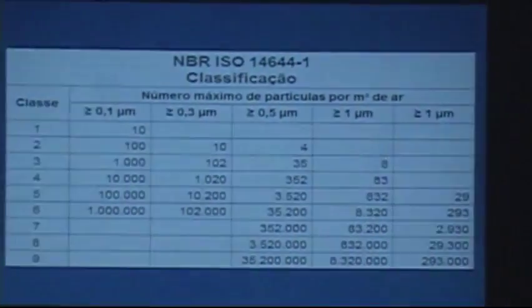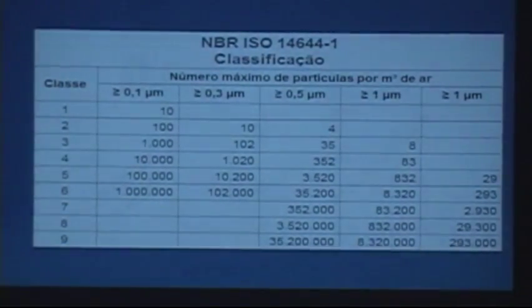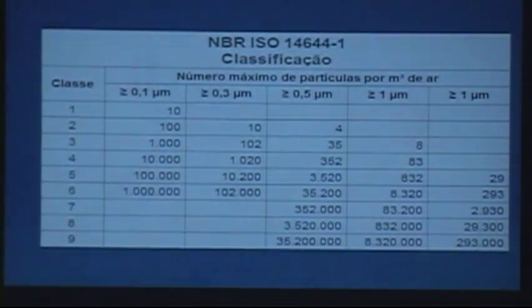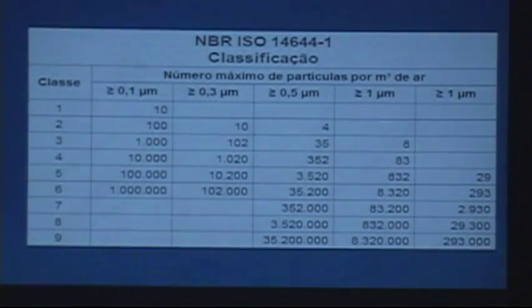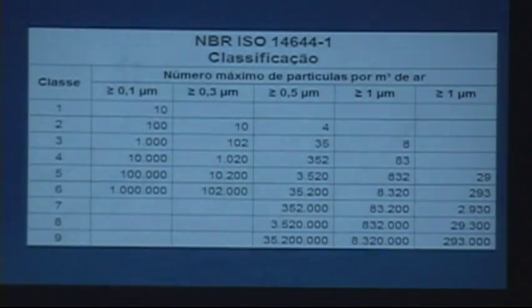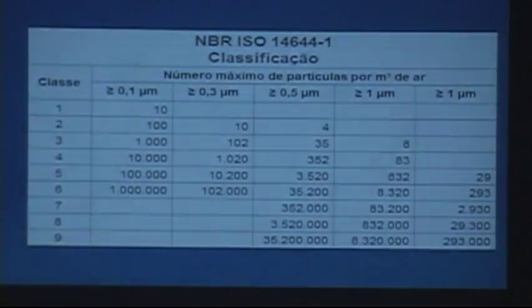But there is a communication between them. So, according to the ISO, we have nine classes of cleanrooms — nine levels. And these levels are established in function of the number of particulates existing per unit of volume. Material particulates that are in the air — viable or not viable.